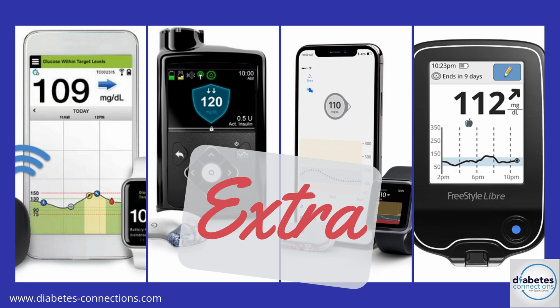Can you tell us how to calibrate accurately? Because I think there is some confusion there, too. Yeah, well, it's very important to use a meter that's accurate. I'm a fan of the Contour Next meter. I feel that's the most accurate one on the market. Make sure your finger's clean when you check and you enter the reading right away. You can calibrate the Dexcom just by going into settings and entering a calibration. That's pretty simple to do. I think a downside to the Libre is that it cannot be calibrated. So if it's not performing properly, if it's running higher or lower than your actual blood sugar, there's no way to fix it.